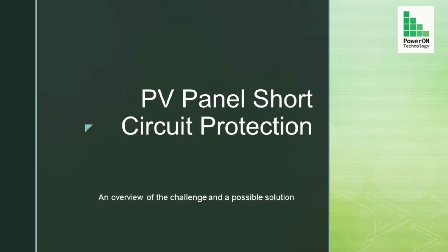Conventional short circuit protection, using fuses, does provide a level of protection, but due to the unique current voltage characteristics of the PV panel, fuse protection is typically delayed and not instantaneous. The PV protection proposed in this presentation is aimed at filling the gap left by fuse protection. The proposal is for faster, more intelligent short circuit protection.